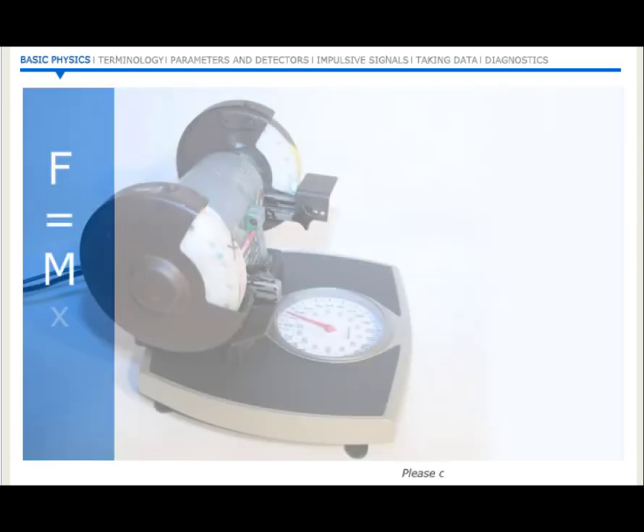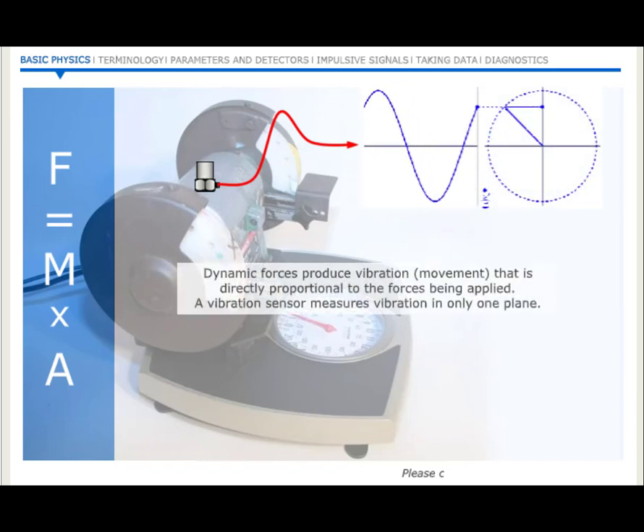In the real world, of course, it's impractical to install scales or some kind of force sensors under the feet of a machine in order to measure the effects of these forces. This would be expensive and invasive. A more practical way to study these forces and resulting motion is to use an accelerometer, which we can position on top of the machine. This is a device which measures, as its name implies, acceleration. It contains a piezoelectric crystal which creates a voltage as it moves up and down. We can capture this signal by connecting the accelerometer to an instrument.